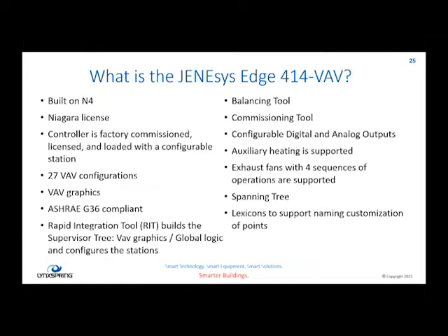The Rapid Integration tool builds the graphics for you. ASHRAE has a guideline 36 that we'll get into a little bit later, but we are guideline 36 compliant. Comes with a balancing tool, a commissioning tool. The digital outputs and analog outputs are both configurable, so you can adapt them to the application that you have. We have auxiliary heating, so you can do a drive open, drive closed, a digital open close valve, on-off relay contact, or a 0 to 10 volt, 2 to 10 volt.